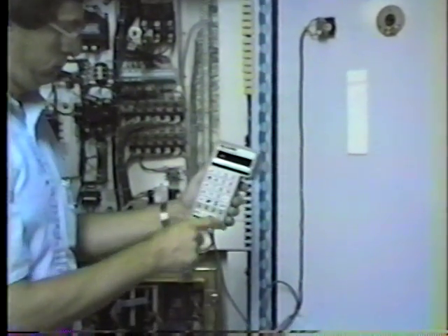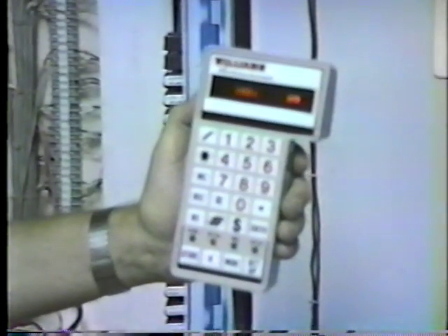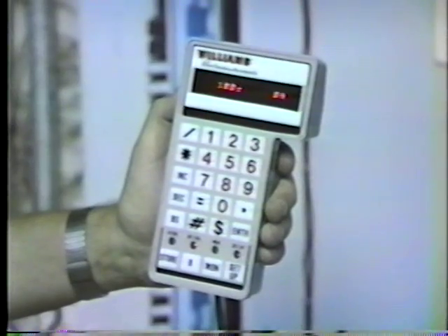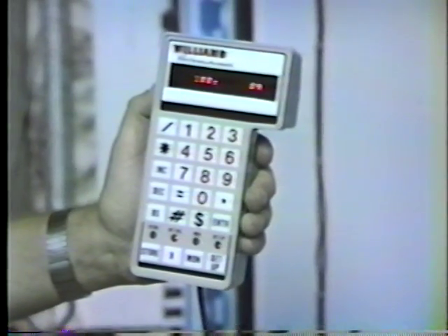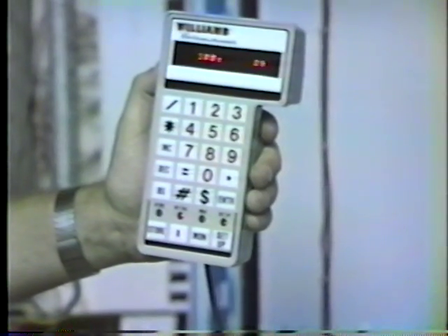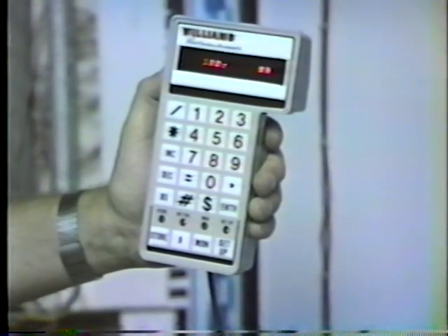Okay, one other thing, is there a timer on this that would tell you how many hours you've been operational? Yes, sir. That's at location 100. Would you show us that? Okay, and right now that shows 0 hours of operation. This would basically tell you how long the machine has been operational. Every hour, the computer writes to the memory bank, the EEPROM, and updates on the hour, or any combination of shutdowns, it will write directly. Any failure, it will write directly.